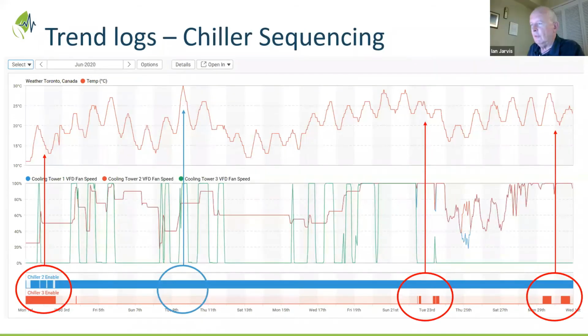And then looking at the way the plant actually operates, it's the same outdoor temperature profile, right? But this is, what do we have here? The cooling towers? So yeah, it is the same. This is another reason why we want to see the trend logs archived at a 15-minute interval for a long period, so you can look at historical data and see how your chiller plant is performing.